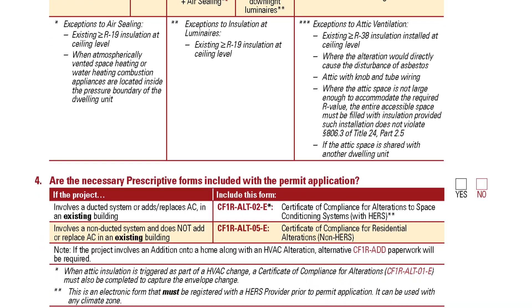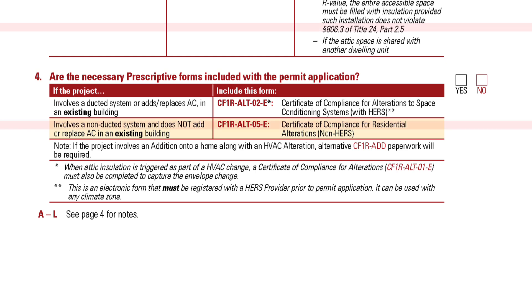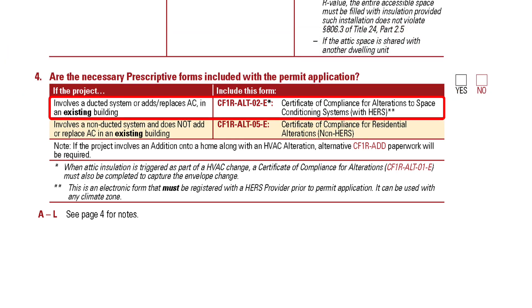The final question to ask in evaluating the permit application is whether all required energy compliance forms were submitted. Part 4 of the checklist page can help with this. Let's say the homeowner didn't submit any energy code forms — what's missing? The table in Part 4 has the required forms by project scenario. In this case, the project involves a ducted system and replaces AC in an existing building, so this project will require submission of compliance form CF1R-Alt-02E.